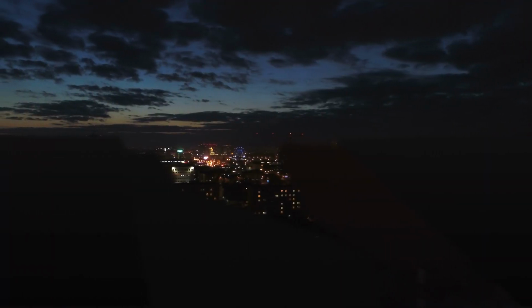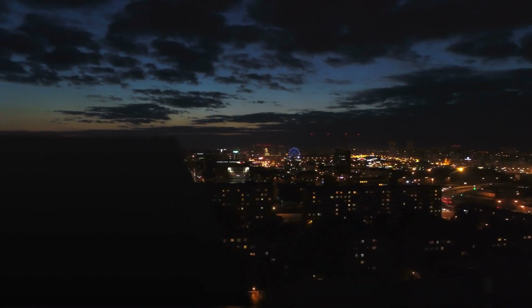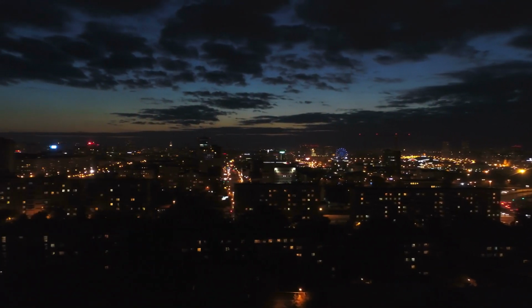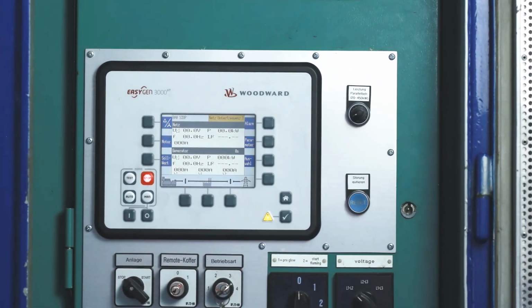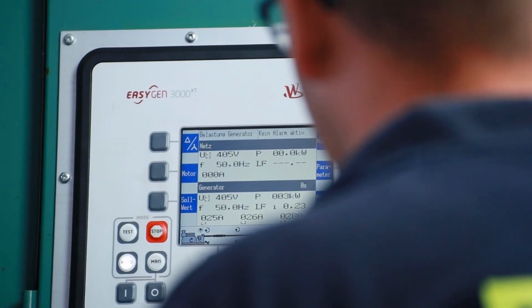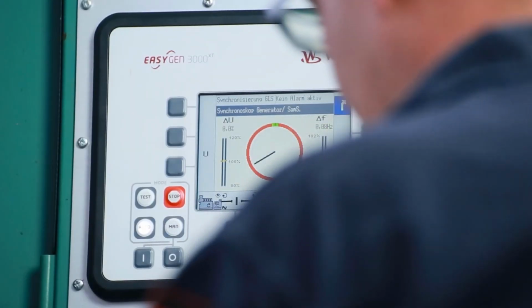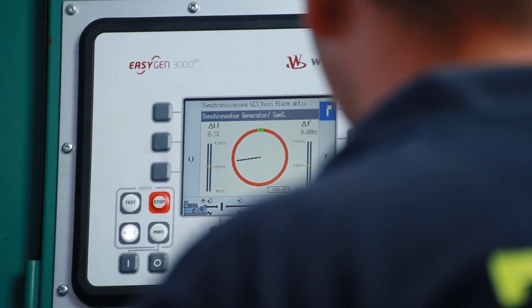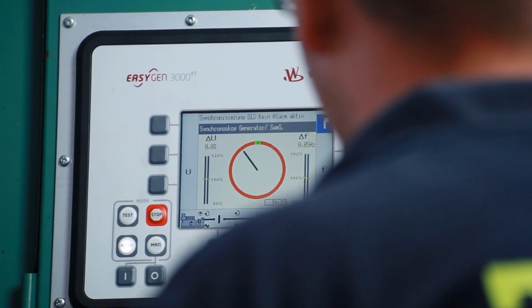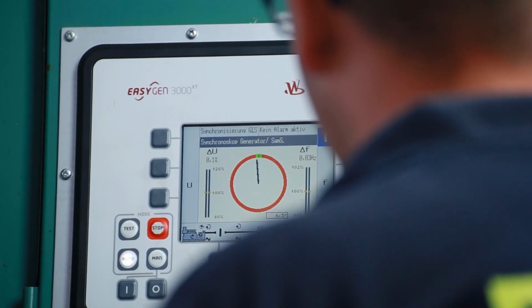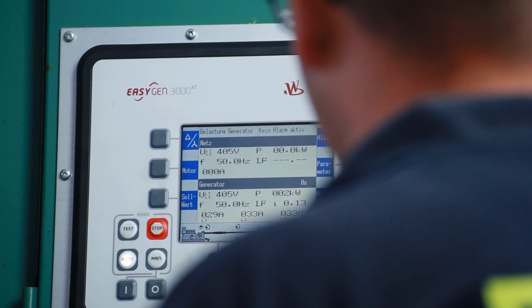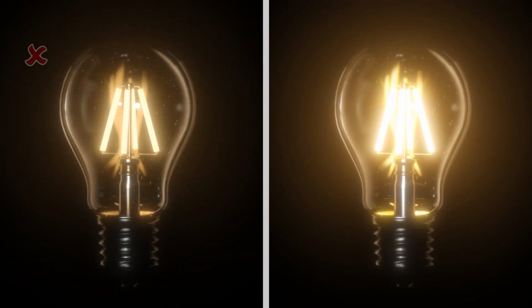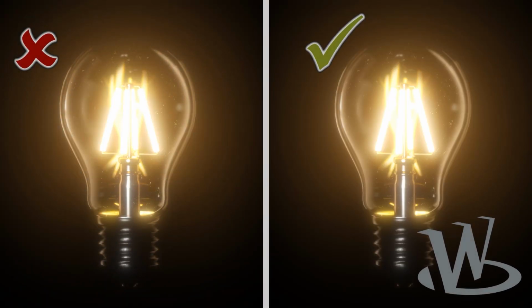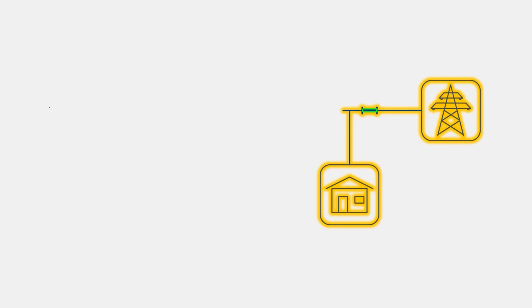While a single generator provides power for a village, a fleet of generators could provide the power for an entire city. The generator control is fully automated, so it controls voltage, frequency, power, and the power factor. It can free up a transformer station without a power outage, and it can later synchronize to the utility, ensuring a seamless switchover to the utility power. So consumers don't even recognize whether the power was provided by a diesel generator. Let's look into how this works.